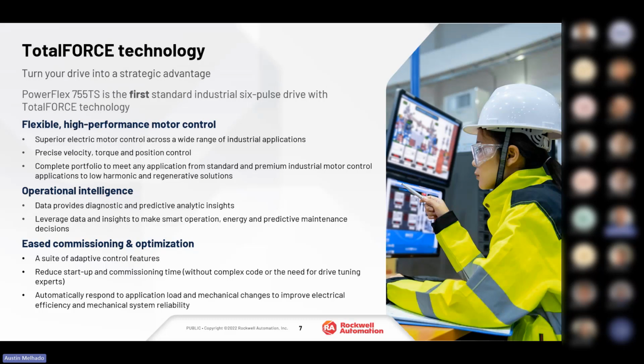Last, ease of commissioning and optimization. This refers to the adaptive control. The drive monitors machine characteristics that can change over time and automatically compensates for those changes. This helps you commission the drive quicker and maintain it for the life of the drive without needing a tuning expert. It also helps reduce mechanical wear and tear and improve uptime.